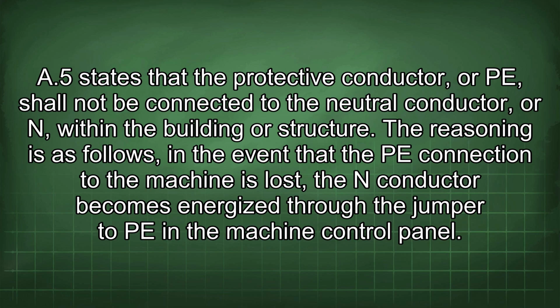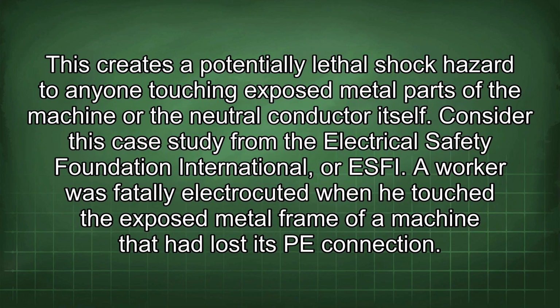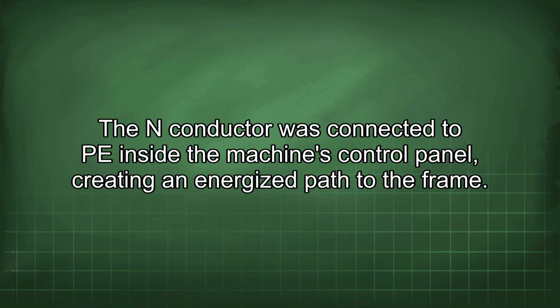The reasoning is as follows. In the event that the PE connection to the machine is lost, the N conductor becomes energized through the jumper to PE in the machine control panel. This creates a potentially lethal shock hazard to anyone touching exposed metal parts of the machine or the neutral conductor itself. Consider this case study from the Electrical Safety Foundation International, or ESFI. A worker was fatally electrocuted when he touched the exposed metal frame of a machine that had lost its PE connection. The N conductor was connected to PE inside the machine's control panel, creating an energized path to the frame.